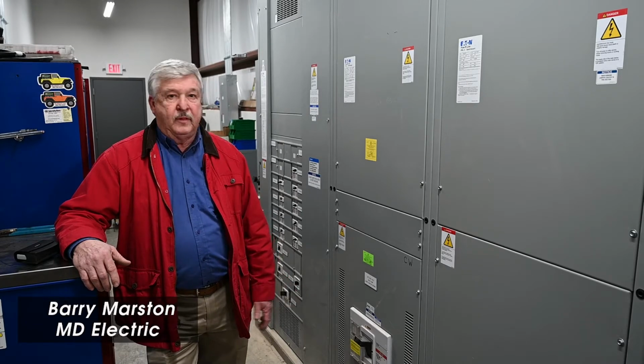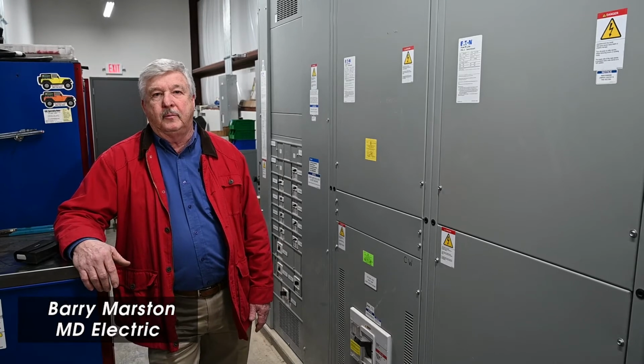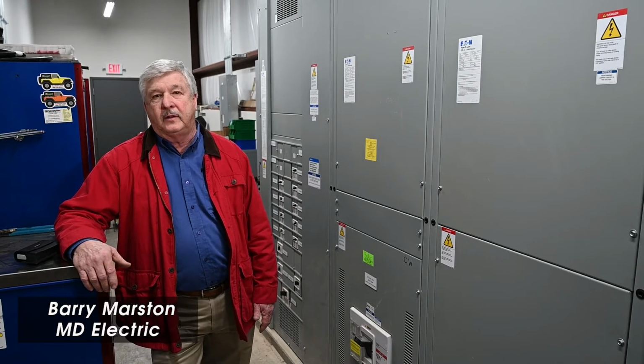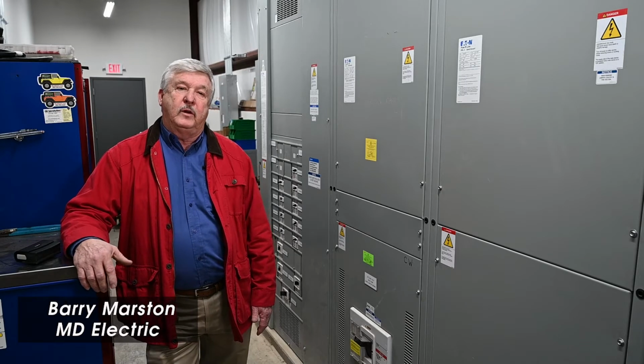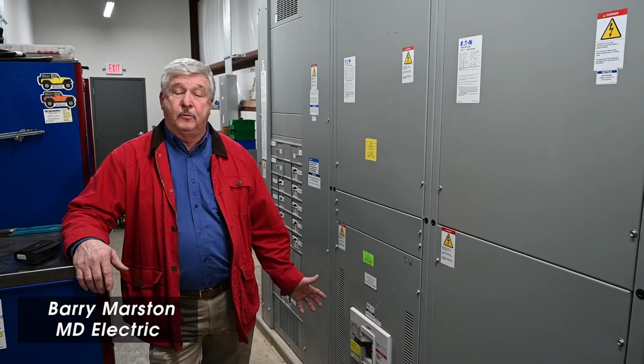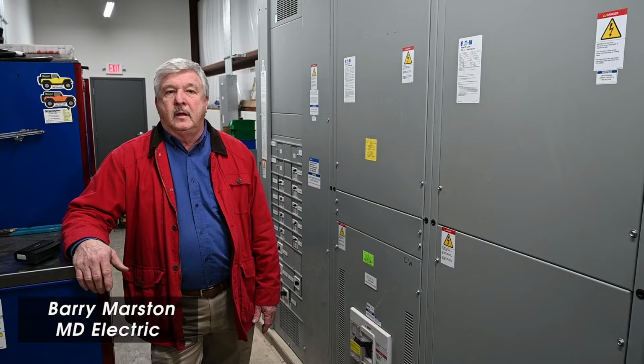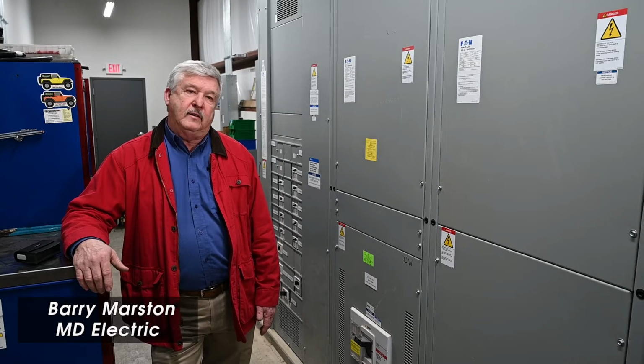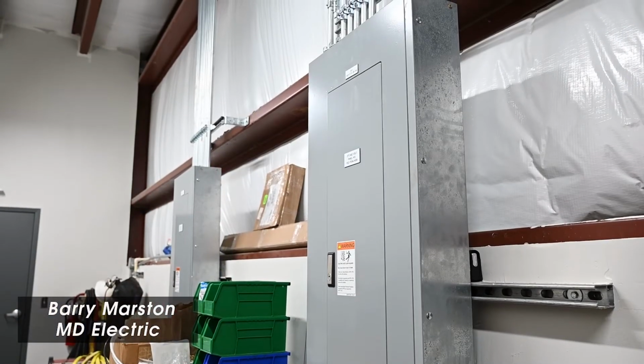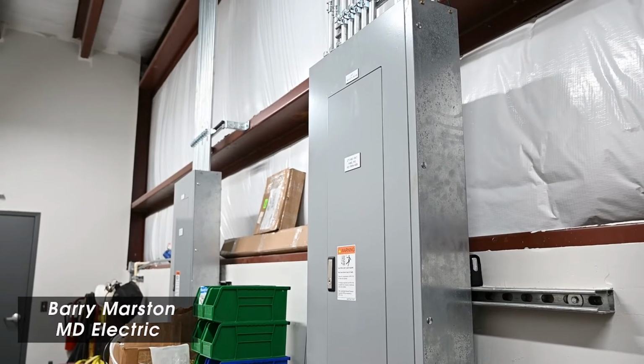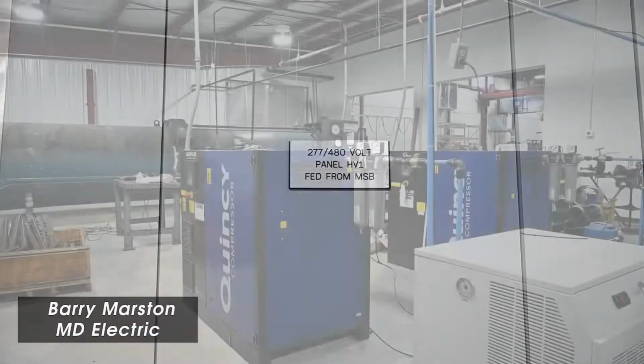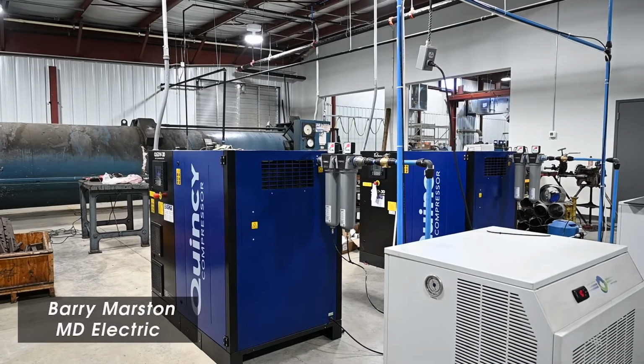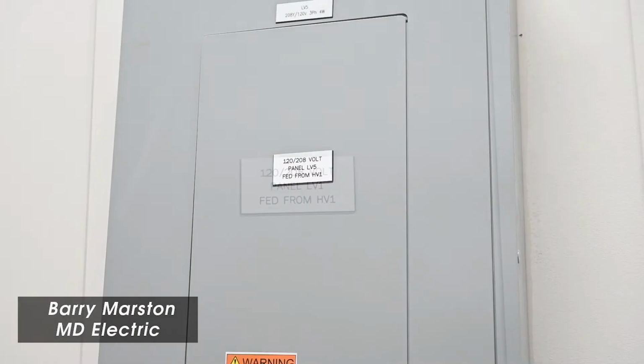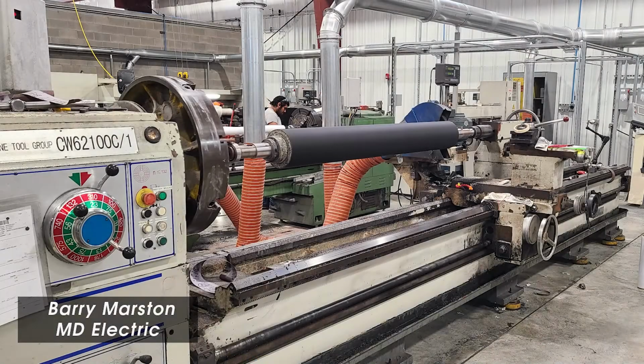It's all labeled: the labels on the panels designate what they're feeding, and at the places that they're feeding, labels designate back to this room where they're fed from. Each one is labeled on top of all the disconnects and panels throughout the building. Panels behind me are HV1, which is a high voltage panel that feeds a lot of the machinery here in the plant. Also, there's LV1 and LV5, which feed equipment and lighting and receptacles throughout the building.